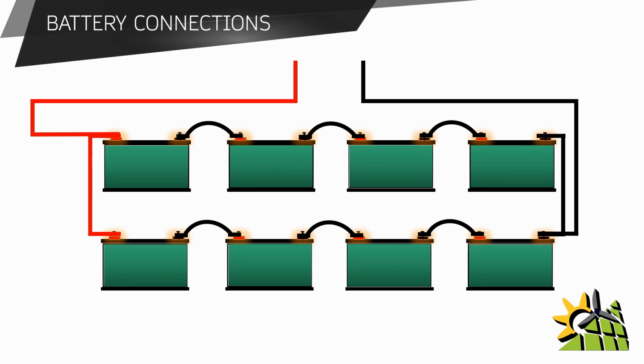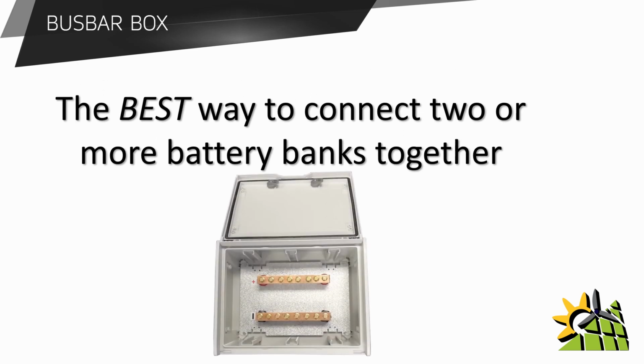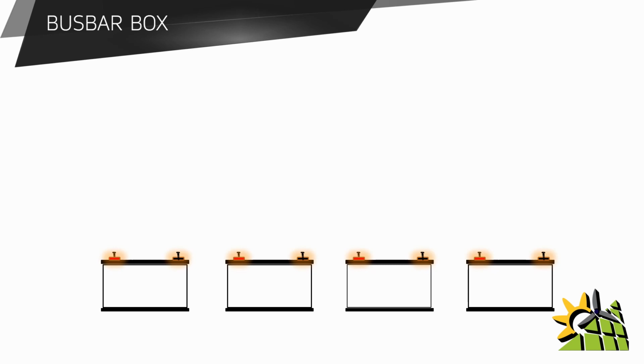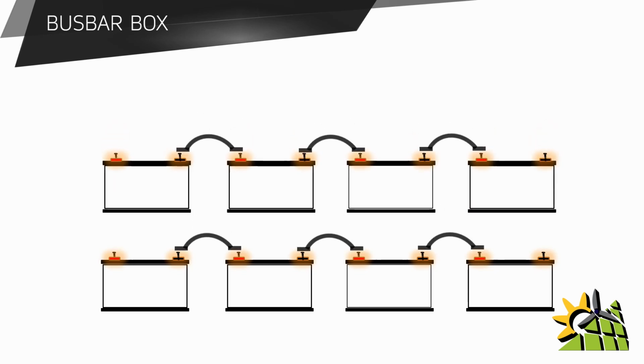The one drawback with connecting batteries in this old-fashioned way is if one of the batteries goes down, it will affect all the other batteries, and you'll need to test every single battery individually to see which one is the damaged battery. A better way to avoid this problem would be to install a battery busbar box. So let me show you how to connect a battery busbar box to two or more battery banks.